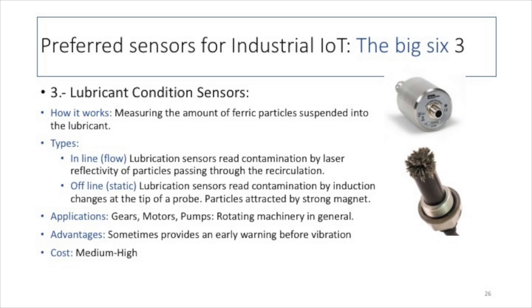So very briefly, we are discussing now the lubrication sensors, and there are basically two types of sensors. The first one, the one you see on the top right side of the slide, is an inline sensor that usually works with a laser source that measures the reflectivity of the metal particles in the lubricant. Of course, this kind of sensor needs an oil recirculating pump in the system, so there is a fluid flow in and out of the sensor.